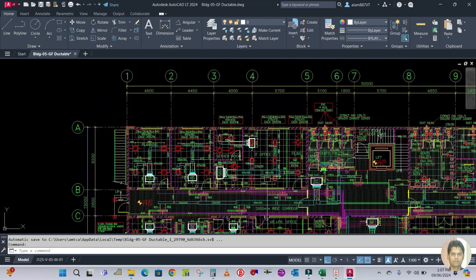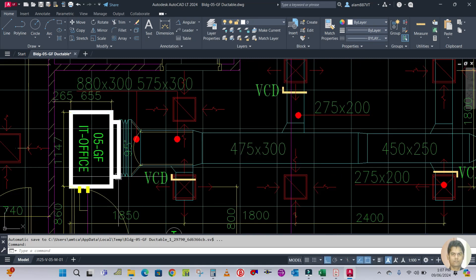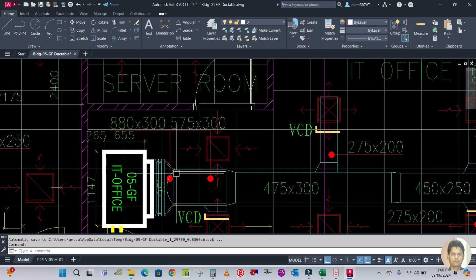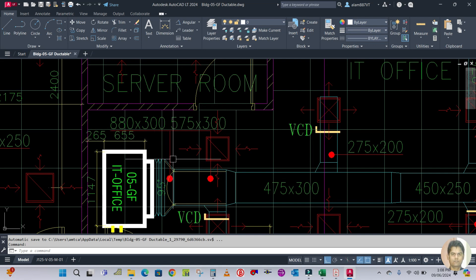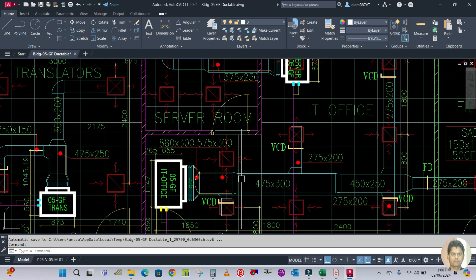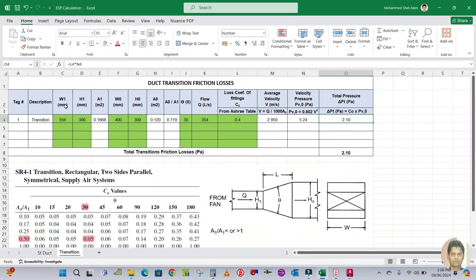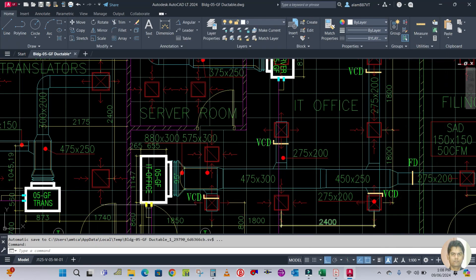Now let us work through an example using one of the design drawings. I am going to take the ground floor IT office FCU. The duct size for the entering portion is 880 by 300 and the duct size for the discharge portion is 575 by 300. Let us calculate the contraction transition piece for this FCU.